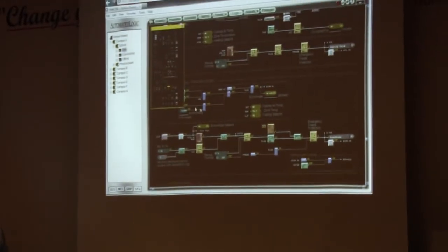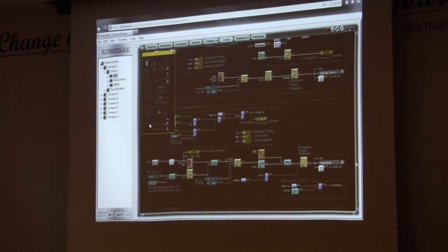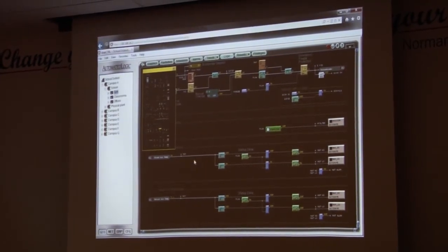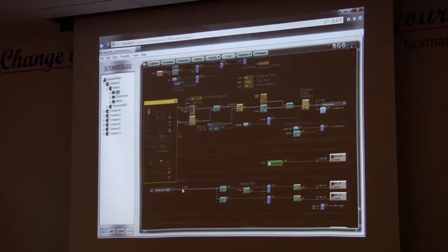Okay, let's go back to our MAT. Let's find out where that's coming from. So if I click on it, I can see this box is flashing yellow, so it's not the one talking, it's the one listening. Let me go ahead and see what it's wire nutted to. Well, here it is, the red one. All right? You got to look on your screen, you'll see it flashing. And I say, well, here, my mixed air temp, here it is here, right? Here's the red one. It's wire nutted to here. These two are connected, right?